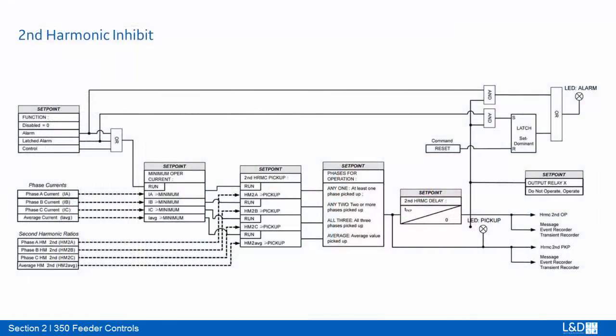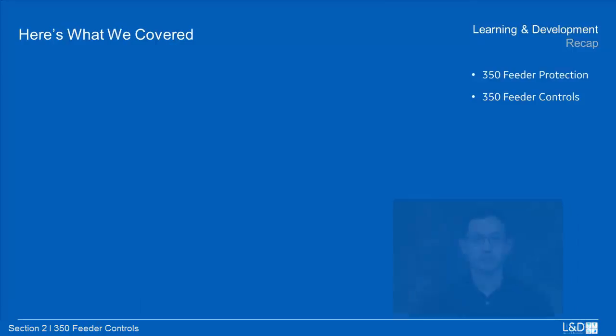Second harmonic operation is based on three conditions: fundamental phase current above the minimum supervision level, second harmonic ratio higher than the setting, and phase selection — any one, two, three, or average that meets the configuration.